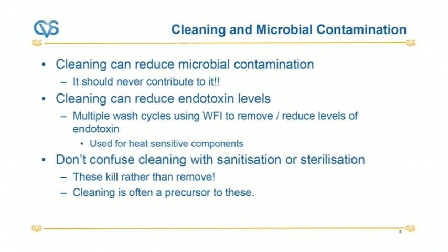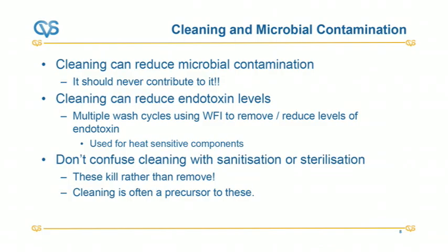Just a little bit about cleaning and microbiological contamination, or microbial contamination. Cleaning can reduce microbiological contamination, but it should never contribute to it. So the last thing we want is a cleaning procedure that contaminates our equipment with microbiological organisms. Leaving a CIP system, or clean-in-place system, wet and standing around for a long time can build up microorganisms that you can then pump into your vessel, and that is not a good idea.